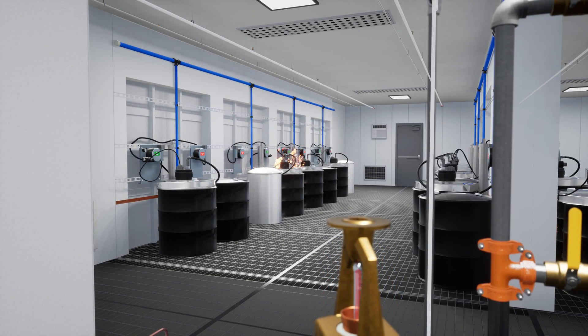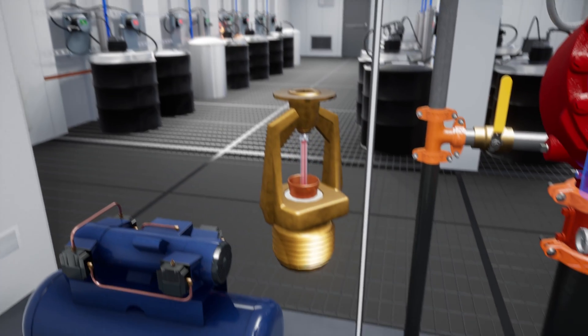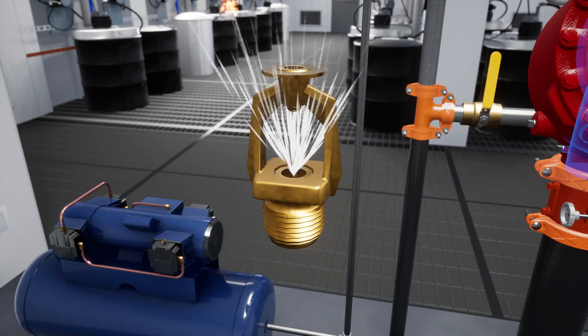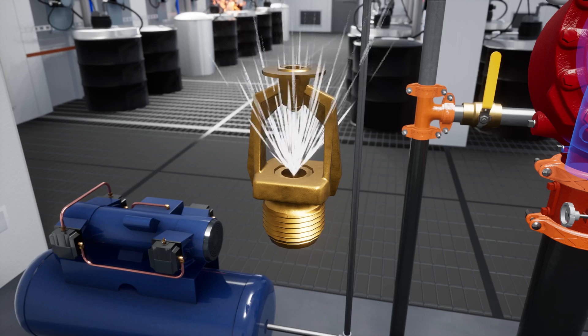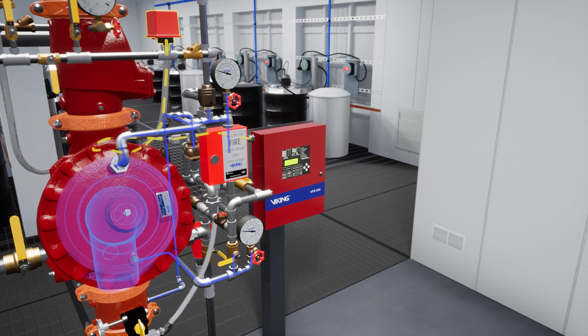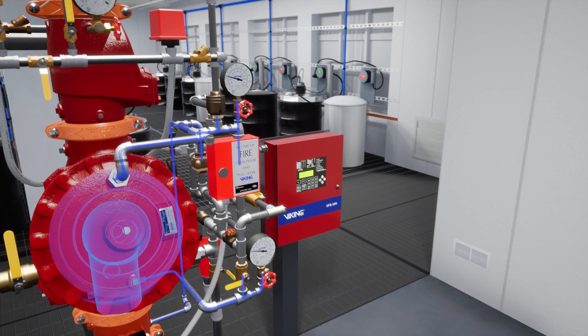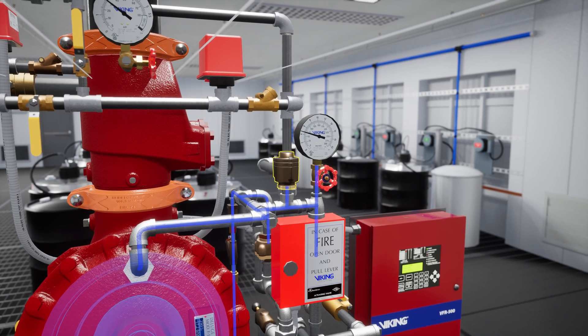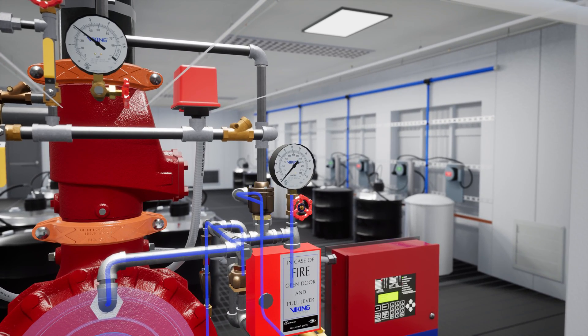In a scenario where a fire has started and the heat increases, the VK800 fixed temperature release activates, releasing air pressure from the pilot line. After the air pressure has dropped enough, the PS40 low air supervisory alarm will be activated, which will send a signal to its monitoring device — in this case a VFR 500 release control panel. As the air pressure in the pilot line falls, the pneumatic actuator will activate, releasing water pressure in the prime chamber.